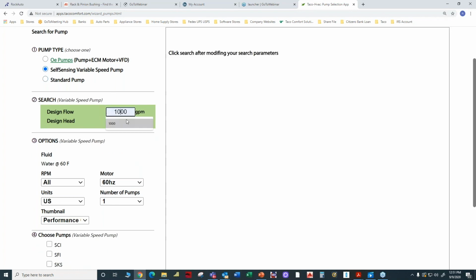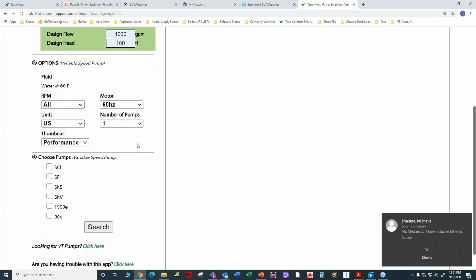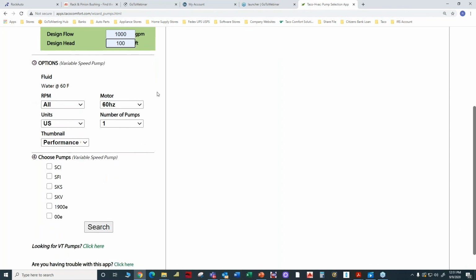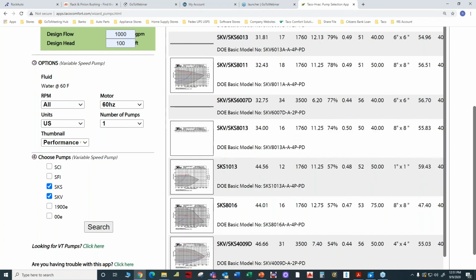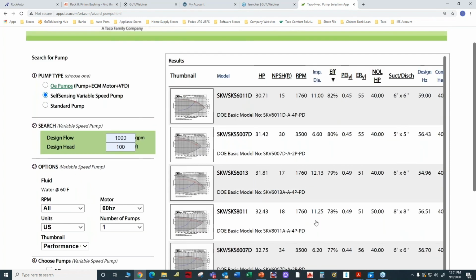And let's say that I had 1,000 gallons per minute at roughly 100 feet of head. I'm going to leave step 3 with these variables. And then I'm going to go to step 4. Let's say I want either an SKS, which is a split coupled vertical inline, or an SKV, which is a close coupled vertical inline. Let's see what the software says is available. I kind of like this one here, just for the fun of it.